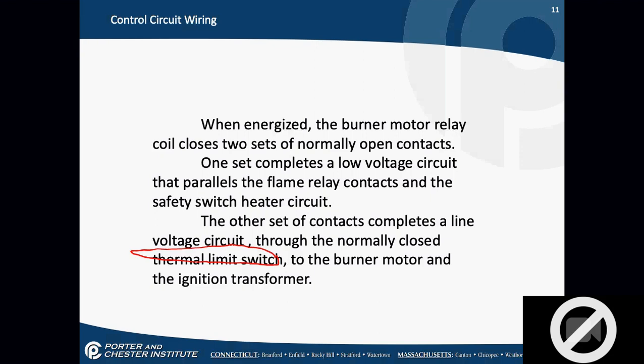Okay, we use a little heater in our primary control to pop a safety switch. It's like a 90-second delay, if that. Most are now running 30 seconds. If the CAD cell doesn't see light, we pop the safety switch, and the motor stops, and we stop dumping unburned fuel into the combustion chamber. Okay, again, we're going to spend a lot more time on that, but I just wanted to show you as best as I can what the parts are.